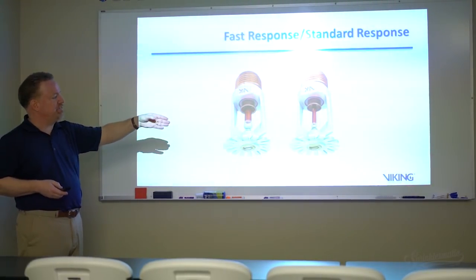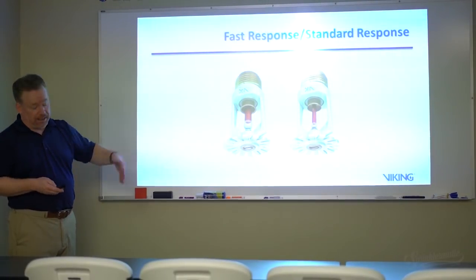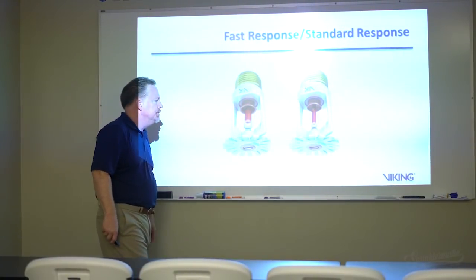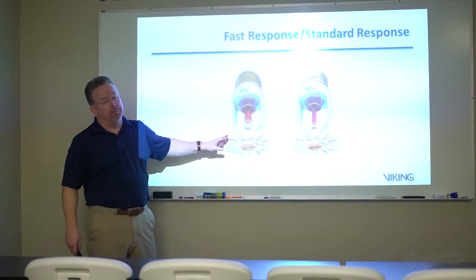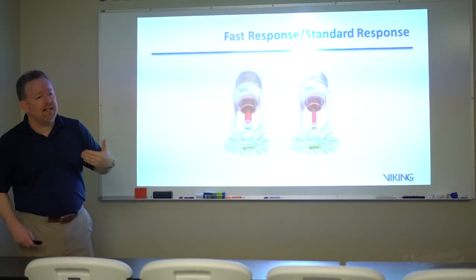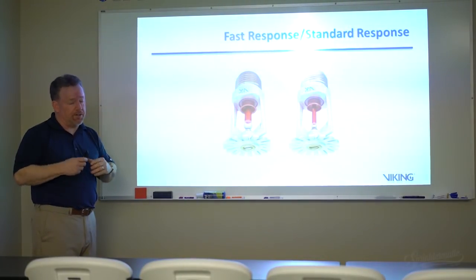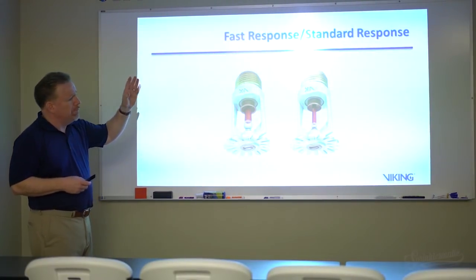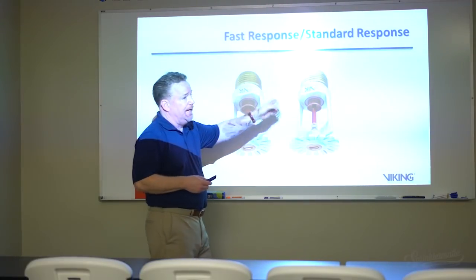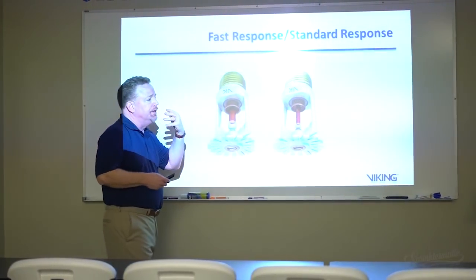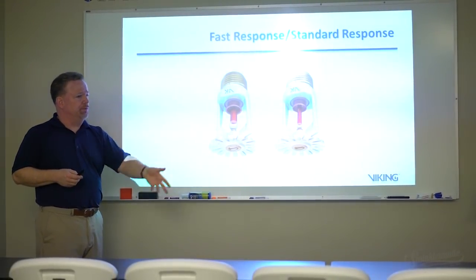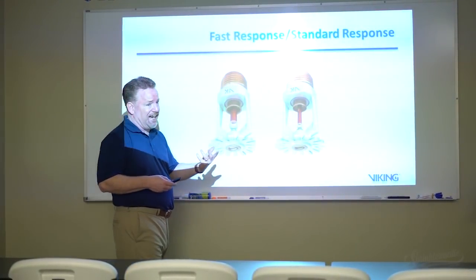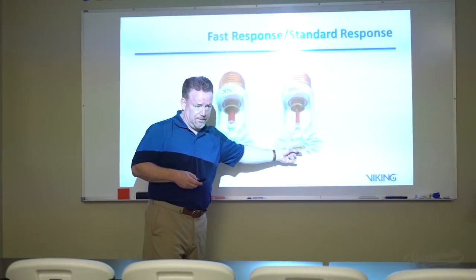Light hazard occupancies — classrooms, office spaces, restaurant seating areas — all require quick response sprinklers. Residential sprinklers, used to protect residential occupancies, are also quick response. As a designer in a light hazard occupancy, you should be specifying quick response sprinklers.